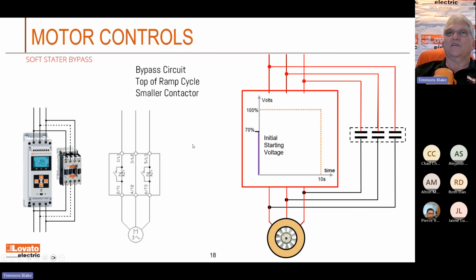So let's look here. What happens if we give it initial voltage? We ramp. When we get to the top of the ramp, the contactor pulls in and it relieves the SCRs of all the load. Same thing on the de-energize. First thing I'll do is de-energize that bypass contactor, and then I'll do the ramp down sequence in reverse.